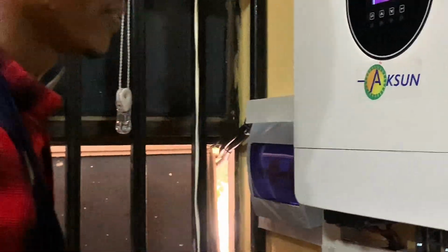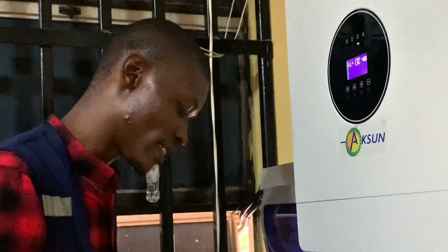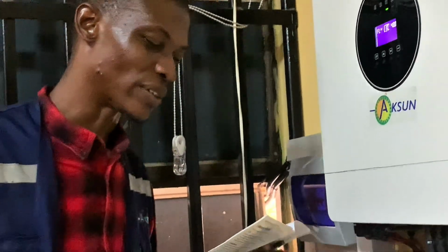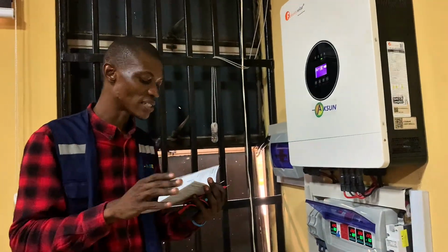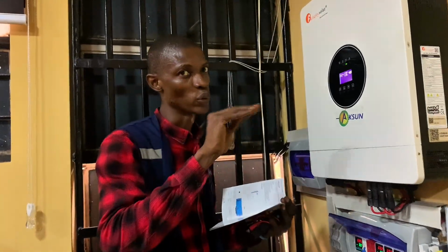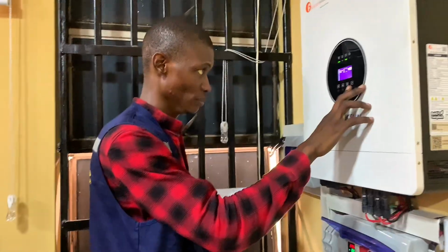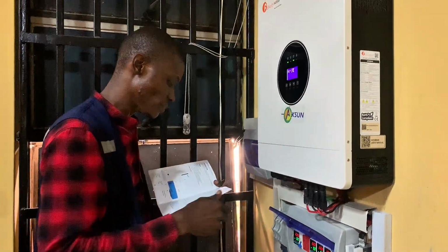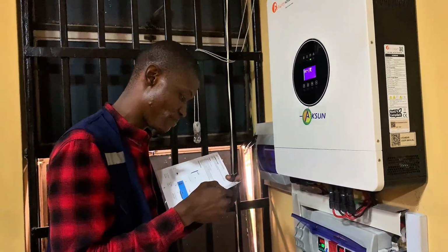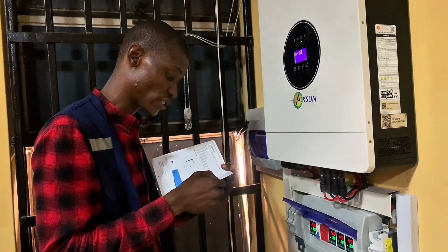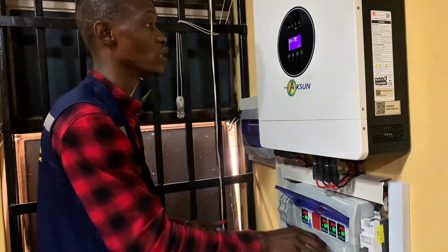So 58.4, we save. And the next one, float charging. Remember this is a lithium battery, so it's always advisable you choose a nominal voltage for your float charging. Based on my type and brand of battery here, our nominal voltage is 51.2.